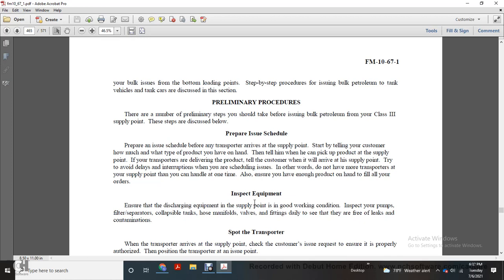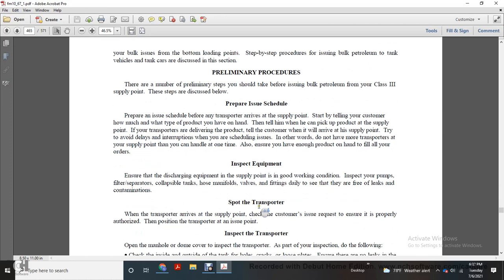Ensure that you inspect your equipment. Ensure that the supply point equipment is in good working condition. Inspect the pump, the filtration, separator, and collapsible hose manifold, valves, and nozzles daily, and see whether they are free of leaks and contaminants.